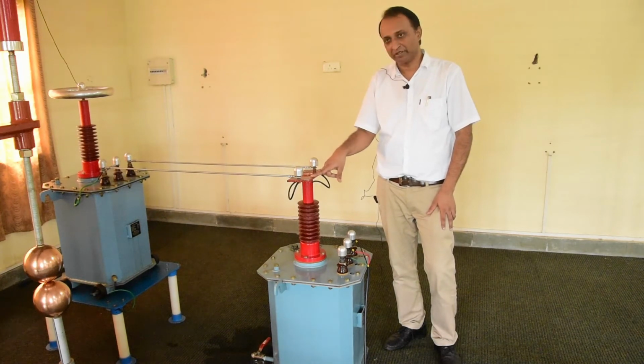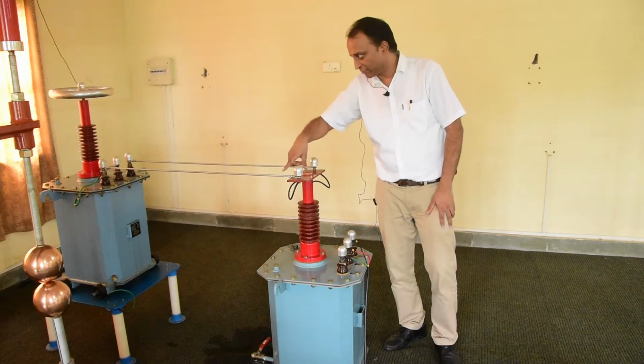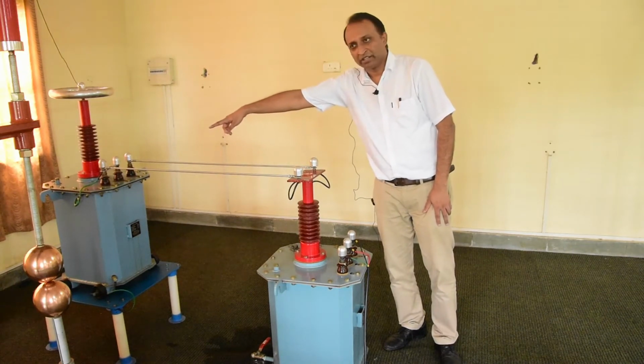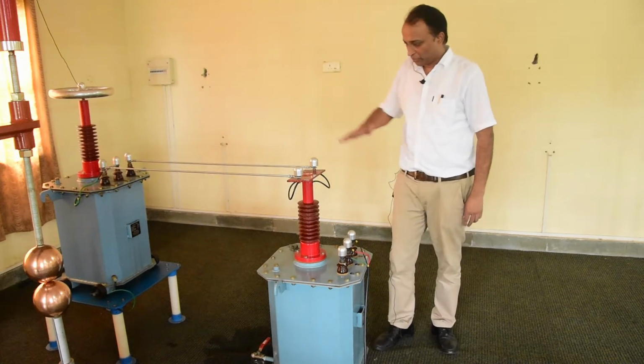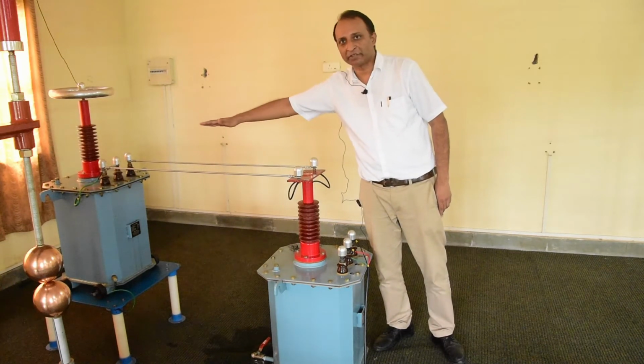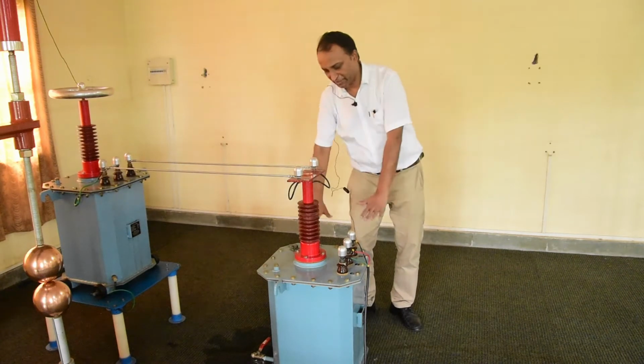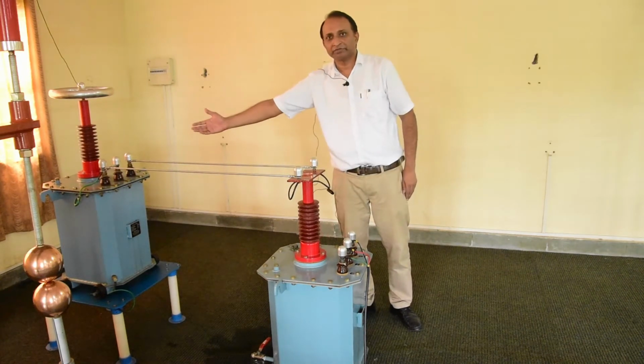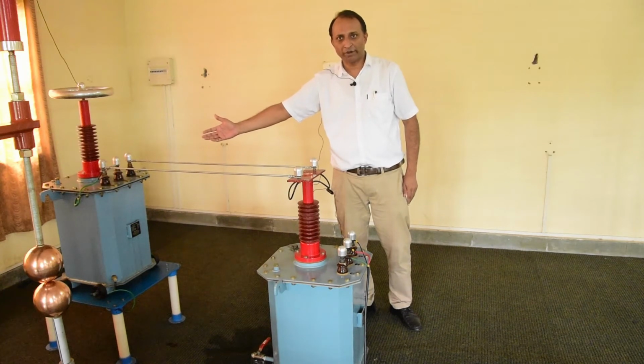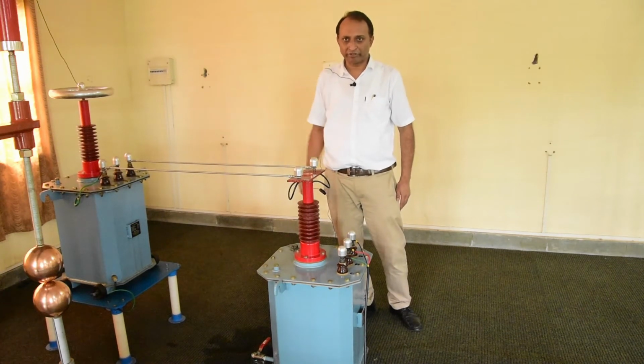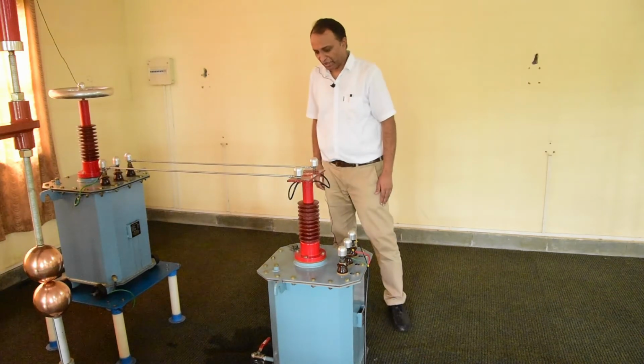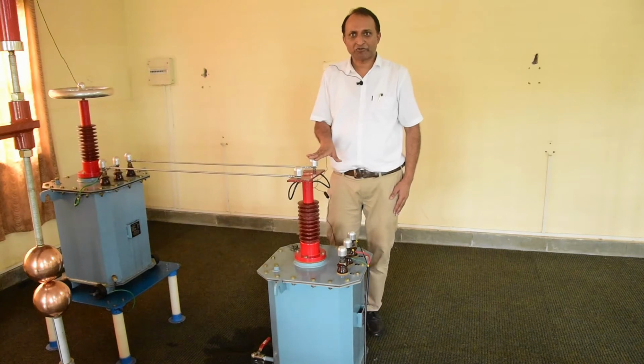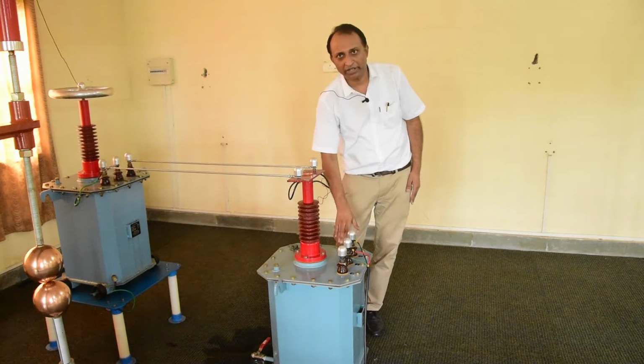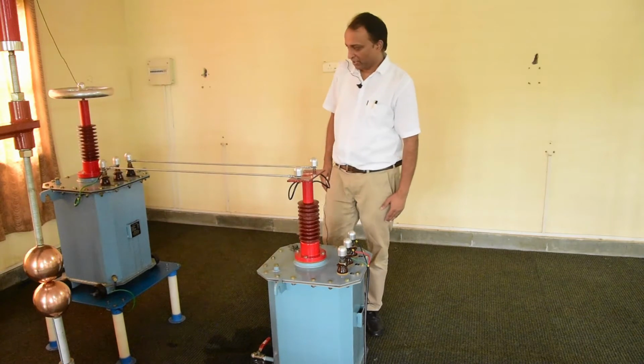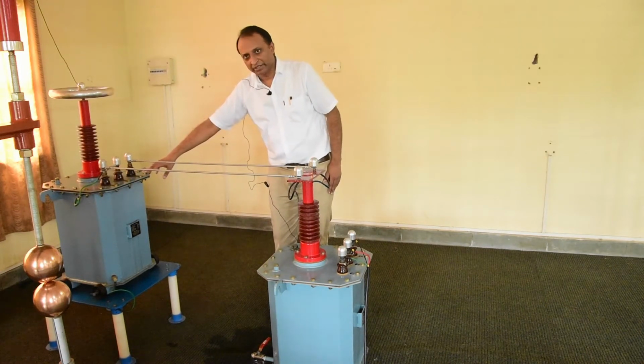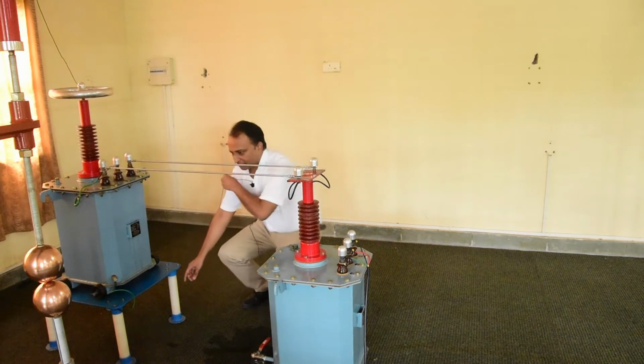Output of the first stage transformer, single phase, will be connected to the second stage. Okay, so output of first stage transformer becomes the reference potential for the second stage transformer. The second stage transformer has similar ratings. Input voltage is 230 volts and output voltage is 50 kV. But the difference, you can clearly note, is that this first stage transformer is installed at the ground potential.